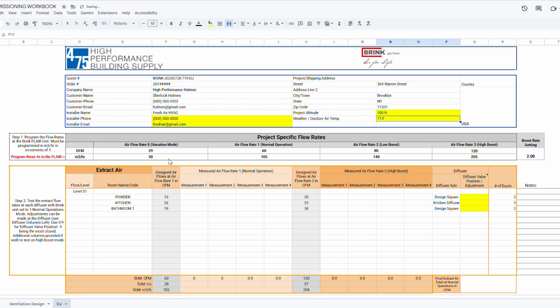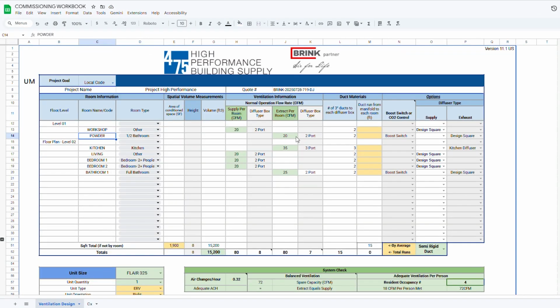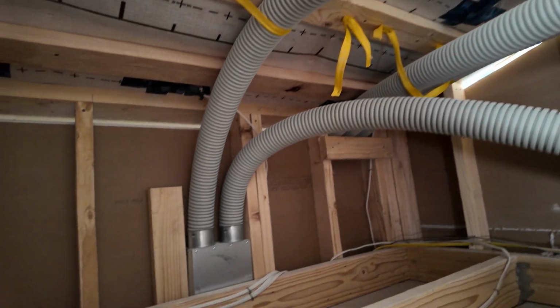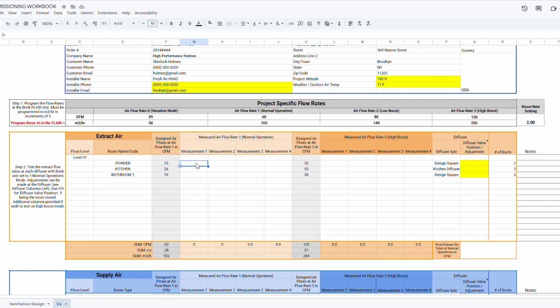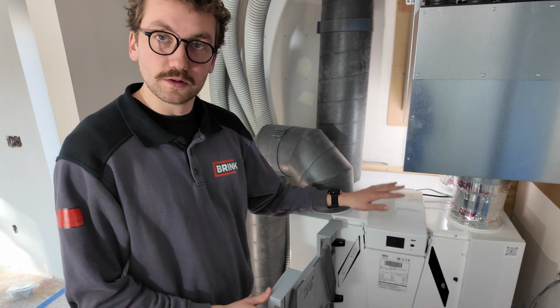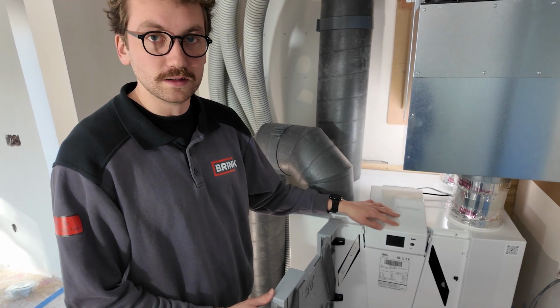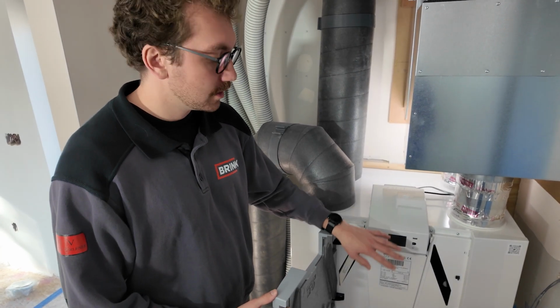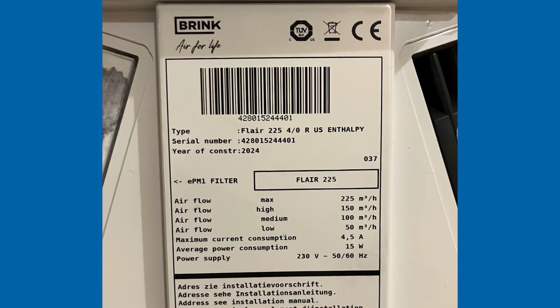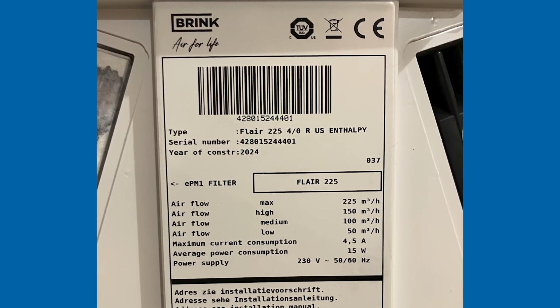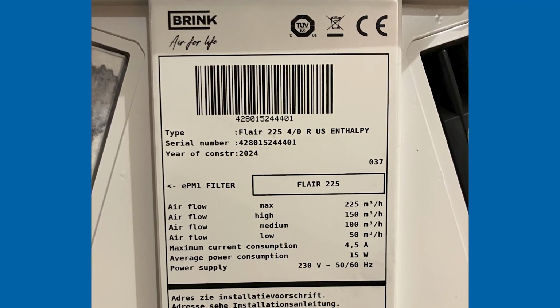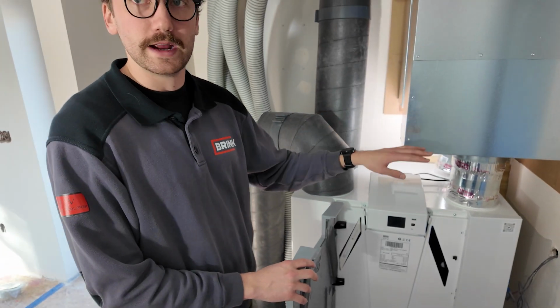During the commissioning process, the agent will verify that everything on site matches the sheet, make notes, and fill in the required information. Perhaps one of the most important things from the commissioning readiness checklist is making sure that the unit that's been installed is the correct model. When we open up the front door here, we have a tag in the center that has the serial number as well as the unit's model number, which distinguishes if it's a left-hand or right-hand unit.